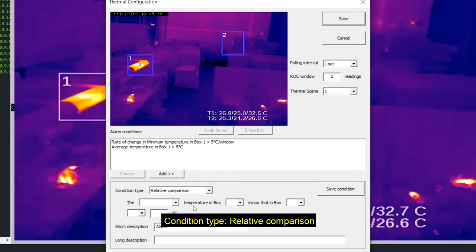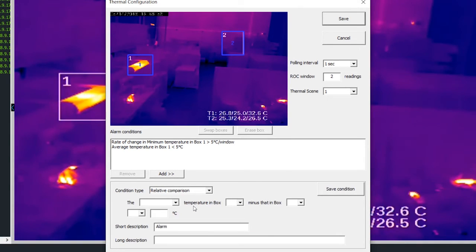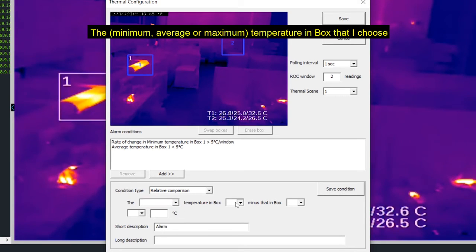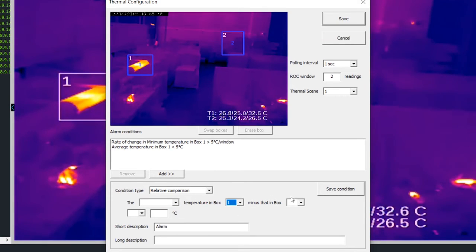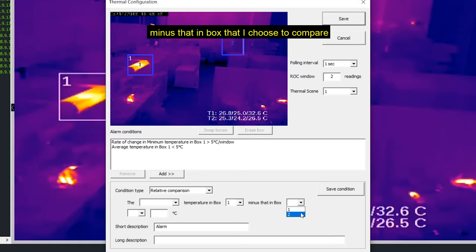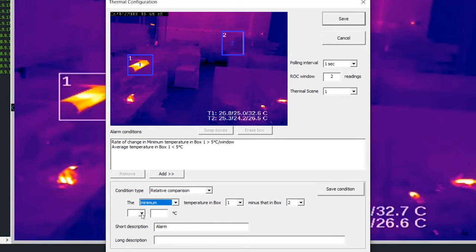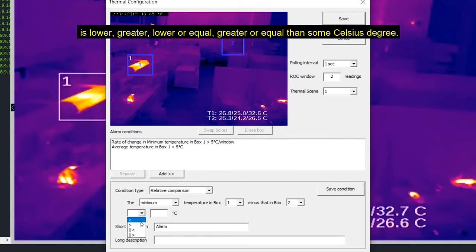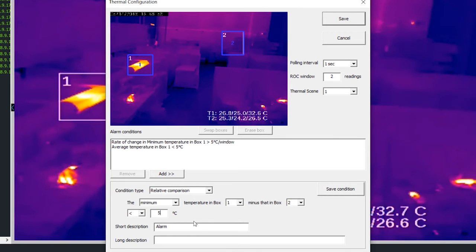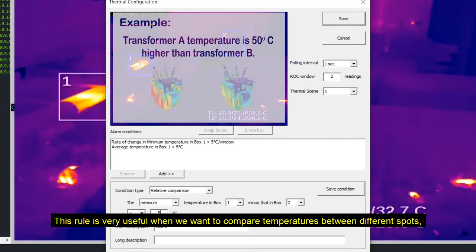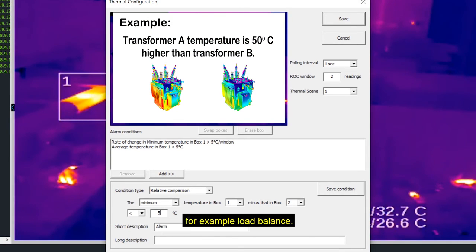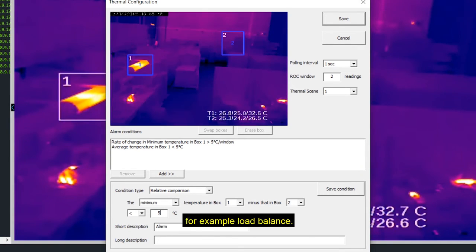Condition type, relative comparison. The minimum, average or maximum temperature in box that I choose minus that in box that I choose to compare is lower, greater, lower or equal, greater or equal than some Celsius degree. This rule is very useful when you want to compare temperatures between different spots. For example, load balance.